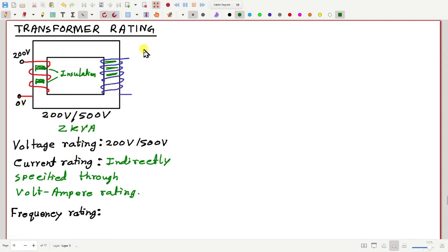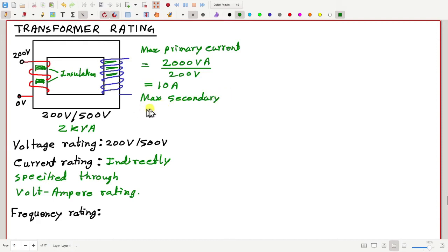So for example, in this case, the maximum allowable primary current will be equal to 2 kVA, that means 2000 volt ampere, divided by the rated primary voltage, which in this case is 200 volt. So that means the primary winding can carry at max 10 ampere current. Similarly, the maximum allowable secondary current for this transformer will be equal to 2000 volt ampere divided by the secondary voltage rating, which is 500 volt, that means 4 ampere.